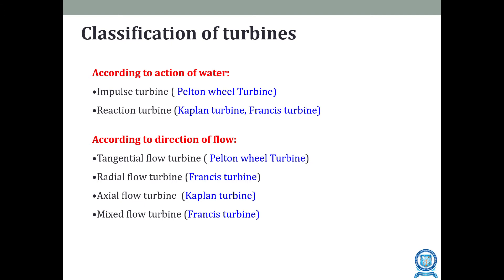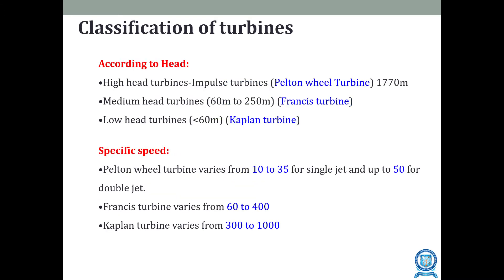We will discuss these types in detail in a later session. According to head: high head turbines operate above 1770 meters and are impulse turbines like the Pelton wheel; medium head turbines operate from 60 to 250 meters, for example the Francis turbine; and low head turbines operate below 60 meters, such as the Kaplan turbine. Regarding specific speed: the Pelton wheel ranges from 10 to 35 for single jet and up to 50 for double jet; Francis turbine from 60 to 400; and Kaplan turbine from 300 to 1000.